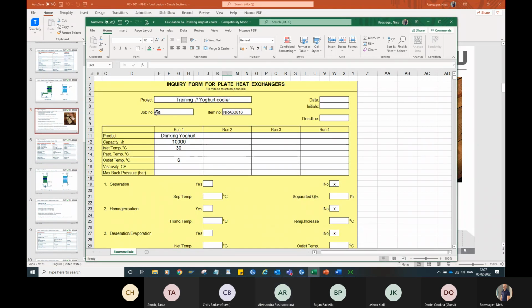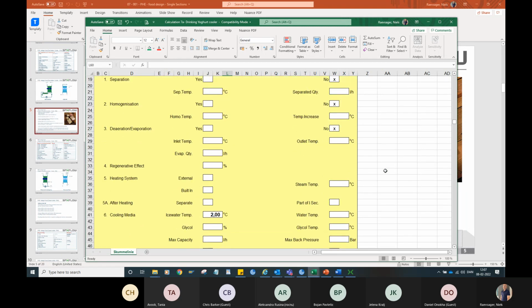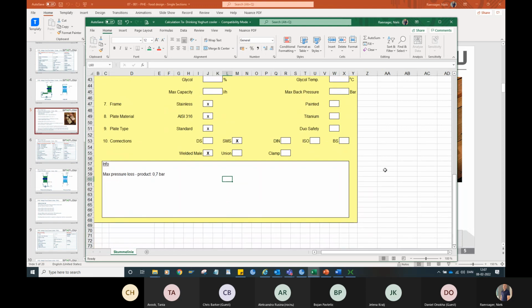You're now going to do calculation 7A, which is a drinking yogurt, 10,000 liters from 30 to 6. Maximum pressure loss on product is 0.7 - that's the requirement on this one.